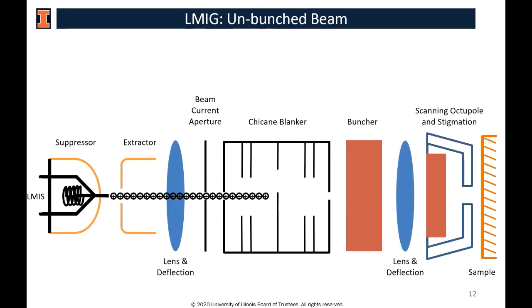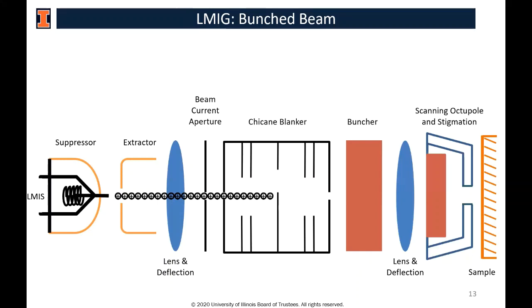Not all ions arrive at the sample at the same time, which reduces mass resolution since secondary ions won't all be created simultaneously. The buncher addresses this by accelerating the last ions through the chicane blanker relative to the first ones. When optimized, all ions arrive at the sample at the same time. However, bunching can increase the beam spot size, so unbunched beams are still used when the highest spatial resolution is desired.